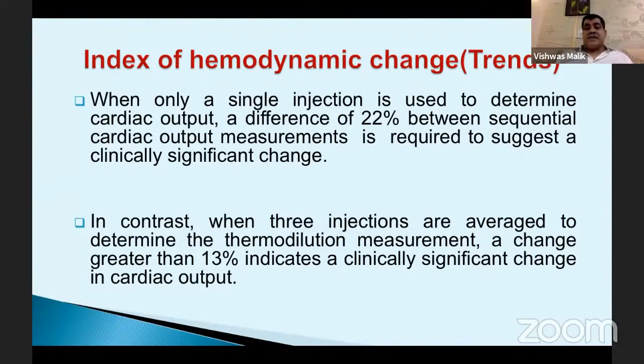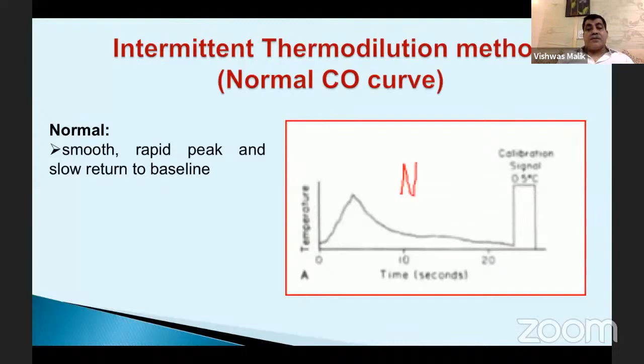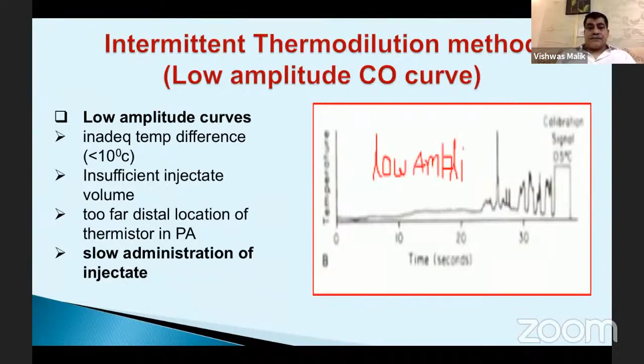So we should know the signature graphs. Whenever we measure cardiac output, this kind of graph is more welcome. It means we know that this cardiac output is going to be reliable. The graph is crisp. It has a smooth, rapid peak and a slow return to the baseline. So this is a normal graph. Whenever there is a low amplitude graph, this means it is not going to give us a good cardiac output value, so we cannot rely on that. However, we need to figure out the reason for this low amplitude graph. This can be inadequate temperature difference, insufficient injected volume, or a slow speed of injection.